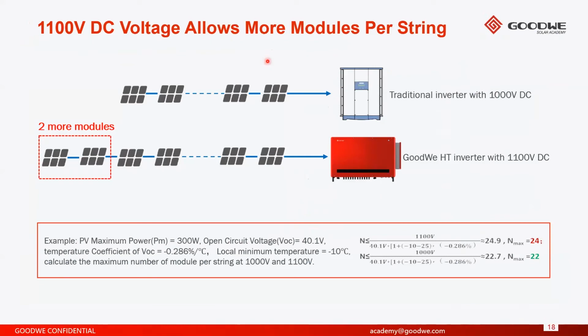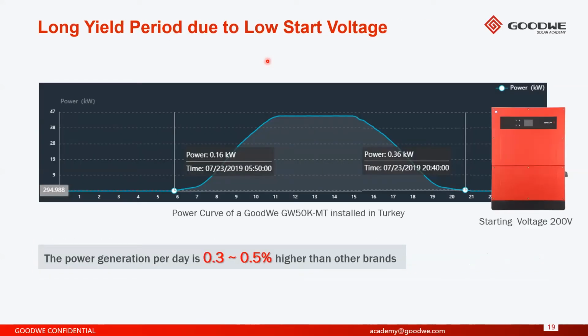Due to the 1100 volt DC voltage, you're actually able to install basically 2 additional panels more than a traditional inverter with a 1000 volt DC input. Our inverters have a much lower startup voltage than most of our competitors. And what you can see is a power curve from an actual PV plant in Turkey. We've calculated that having an earlier startup voltage allows you to increase not your efficiency, but your yield by 0.3 to 0.5%. As you can see, the MT inverter has a startup voltage of around 200 volts. So in the mornings, the inverter does start up earlier, and it's able to run a lot later into the evening.